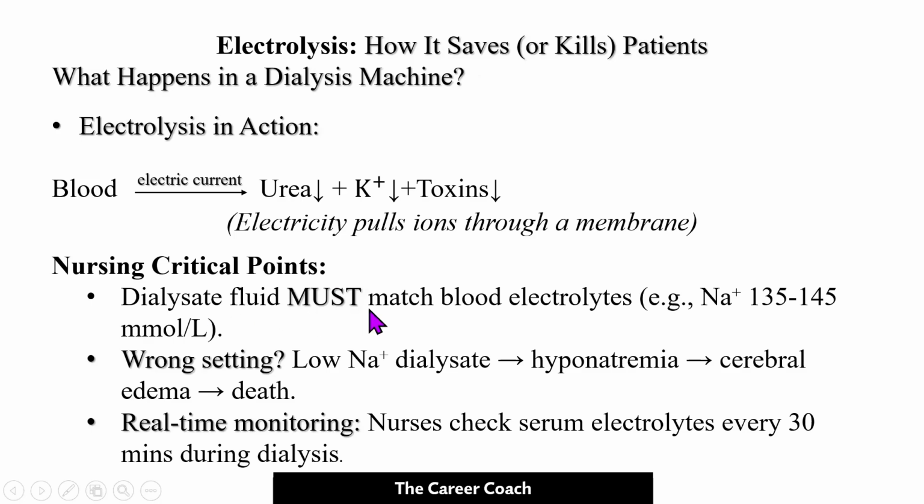Dialysate fluid must match blood electrolytes. A dialysate fluid is the fluid that is used to remove these toxins from the blood. When preparing them, they must match the blood electrolytes. For instance, sodium ion must be between 135 to 145 millimoles per liter.